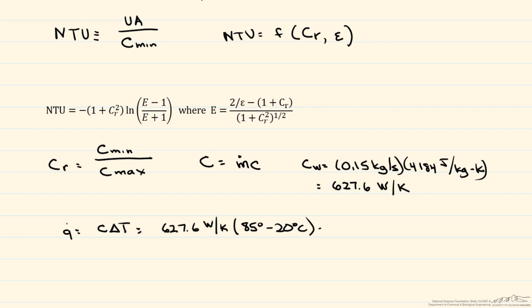So this is equal to 627.6 watts per K times the difference in temperatures, which is 85 minus 20. This is in degrees Celsius. Our Q dot is equal to 40,794 watts. We assume a well insulated system, heat exchanger should be well insulated.